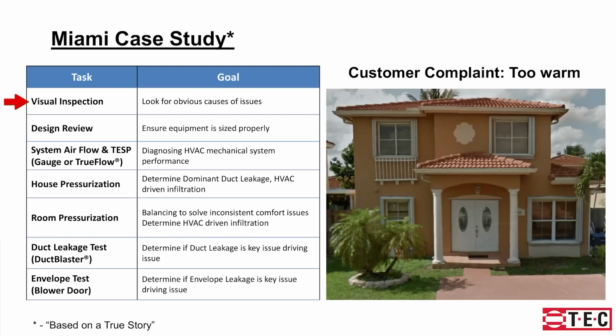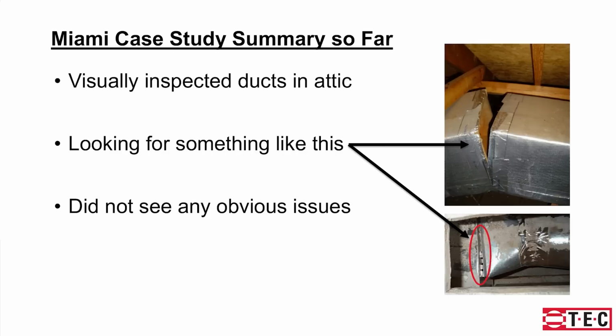So the first one, you might just do a visual inspection. Look for, are there disconnected ductwork in the attic? Do you have a system that has a line that's freezing? Just visual inspections can tell you a lot. Okay, and we'll talk through each one of these. So the visual inspection, if you crawl into an attic and you see this, okay, that's a reason a system would not be keeping up, right? If you see a big gap in the ductwork, you're losing tons of the air out that leak, and that's going to cause the system to not keep up.